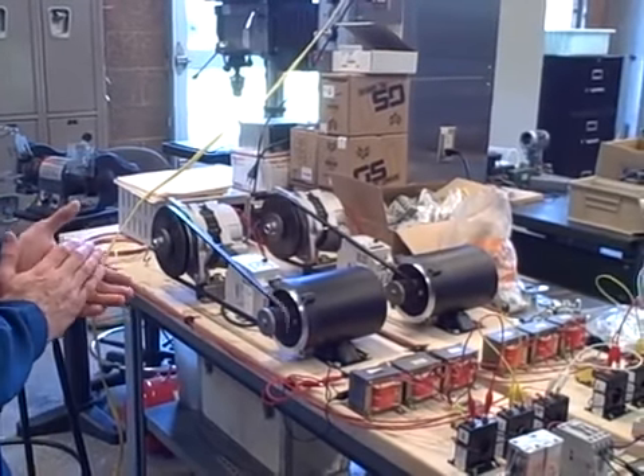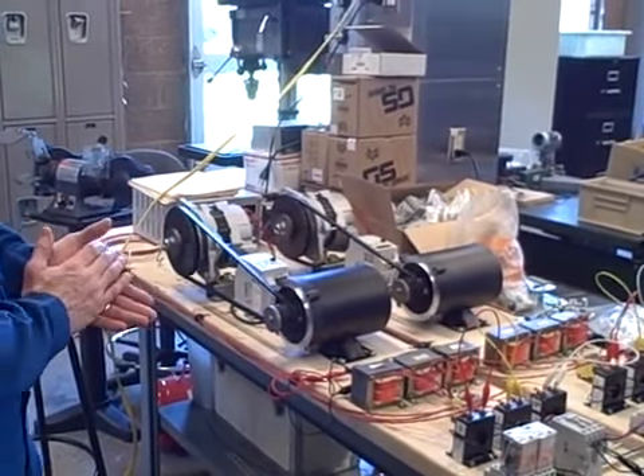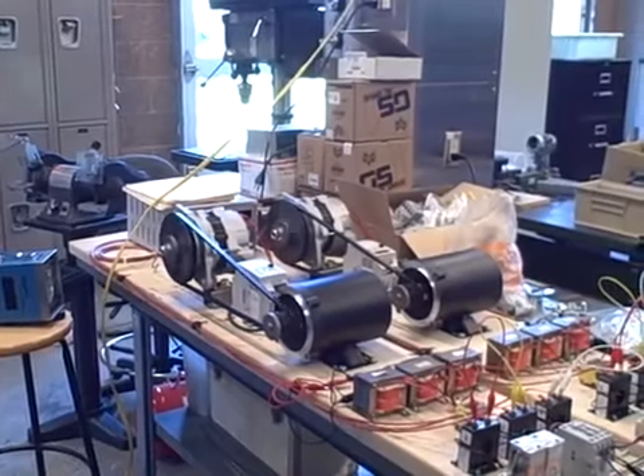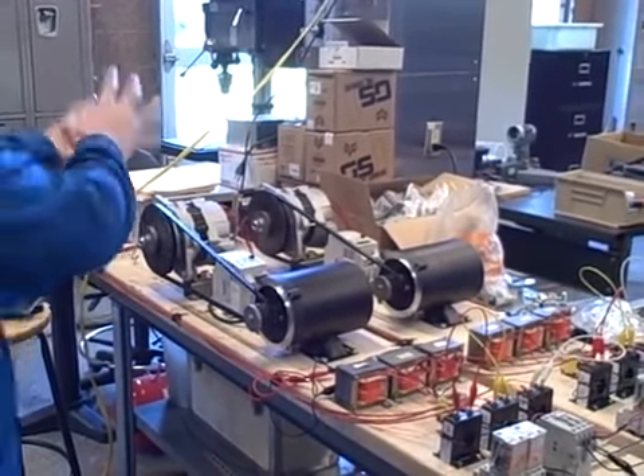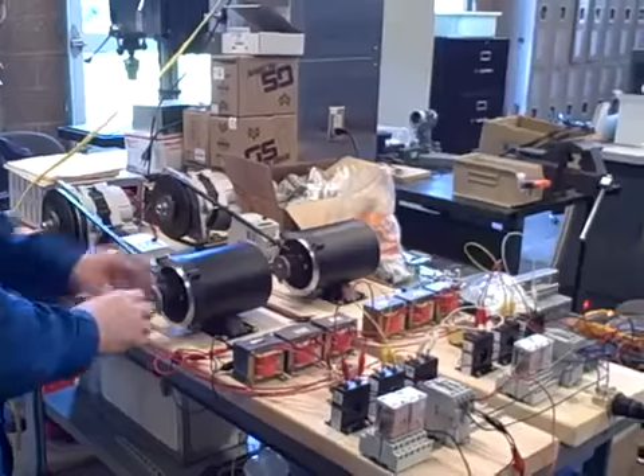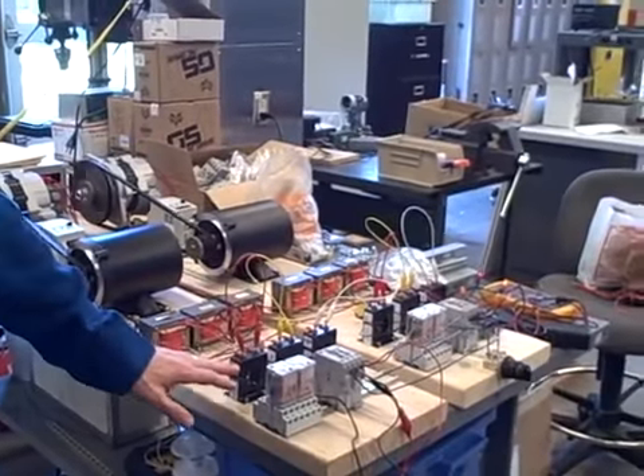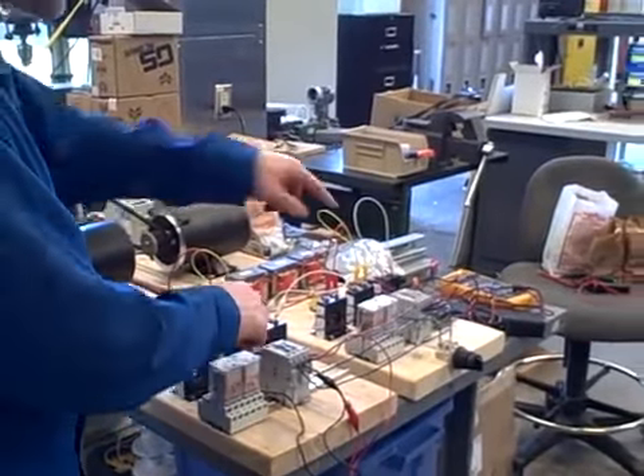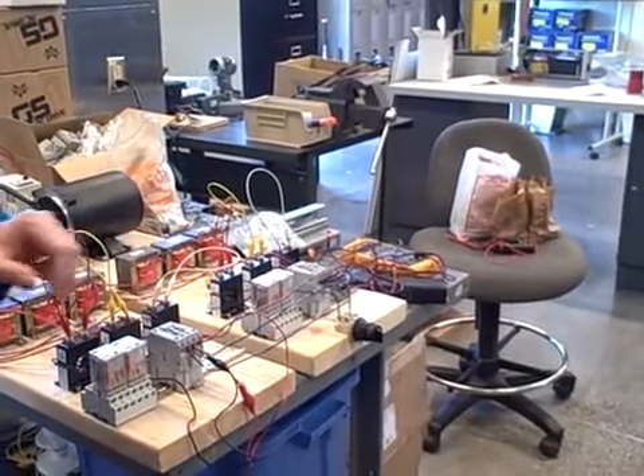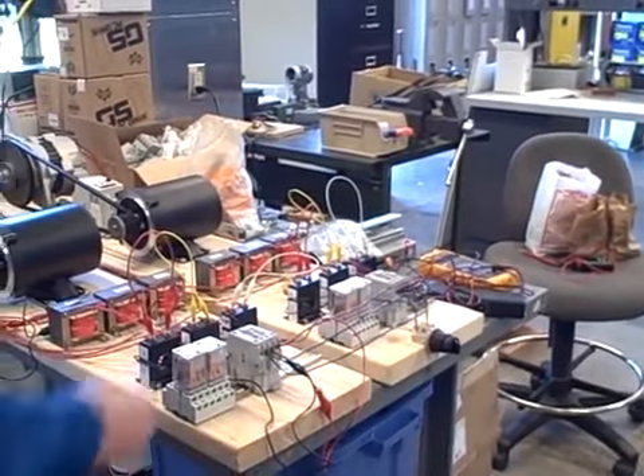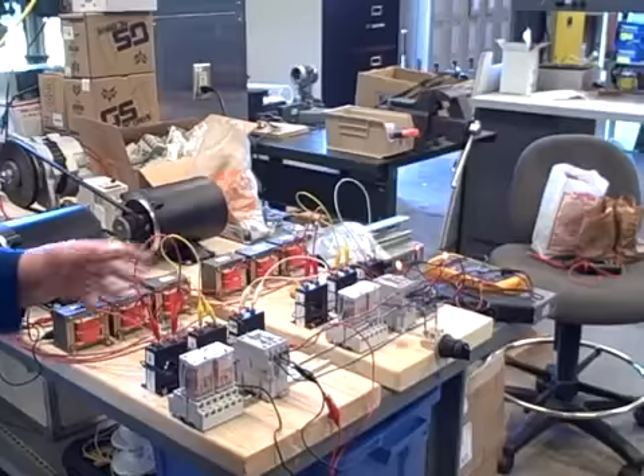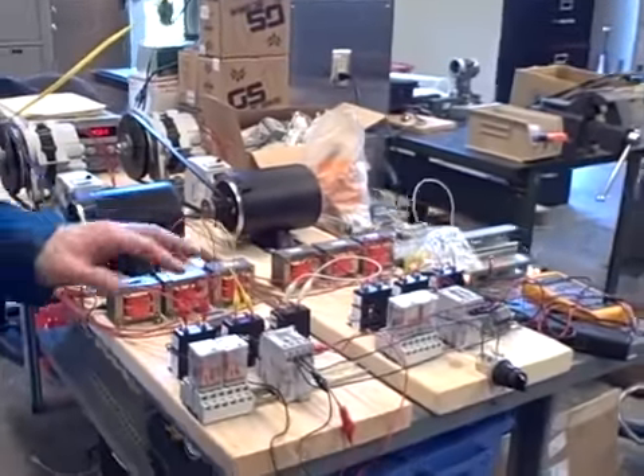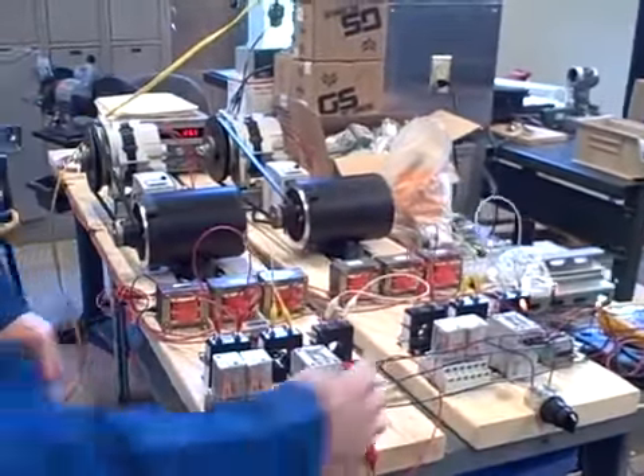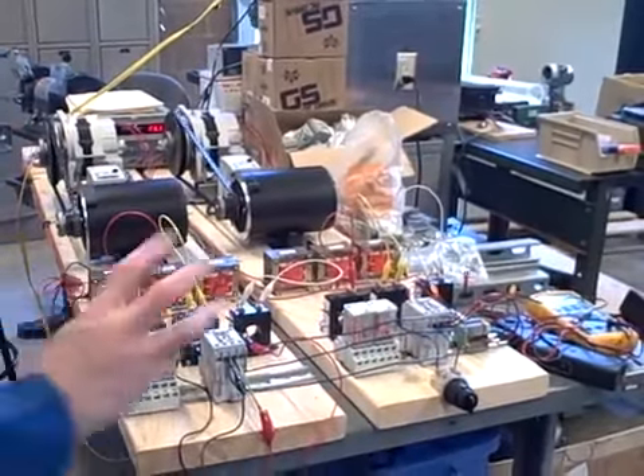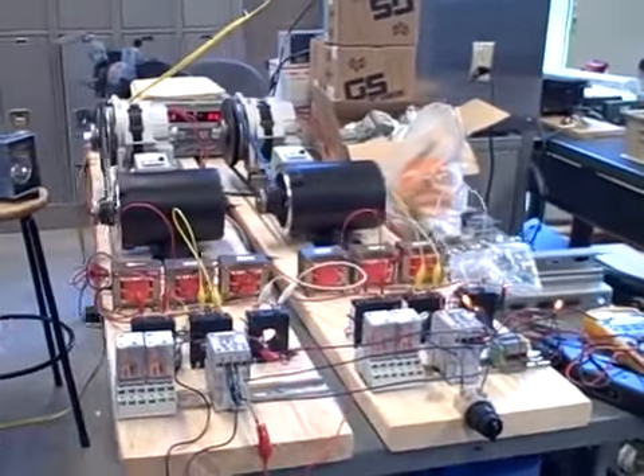What we're going to be doing here is using these to demonstrate power grid operations, and in this case today, synchronizing. So just to show you, we've got the generator, the motor, our speed control, step-up transformers, some current transformers to measure the current, and then we have our circuit breakers. We're using a pair of three-phase contactors as circuit breakers. I'm going to close one of them here, and we've got it set up to be self-latching. Right now, this generator's output is powering this grid, those three wires you see right there, three-phase power, with about 140 volts or so.